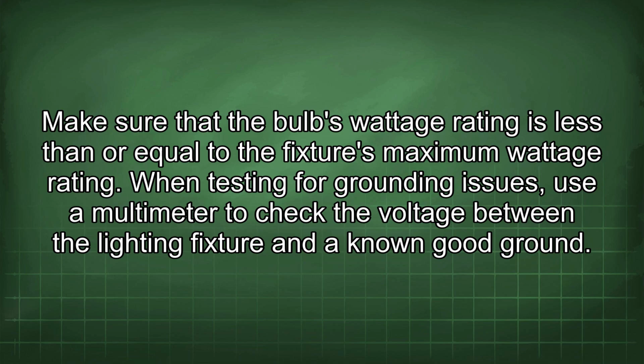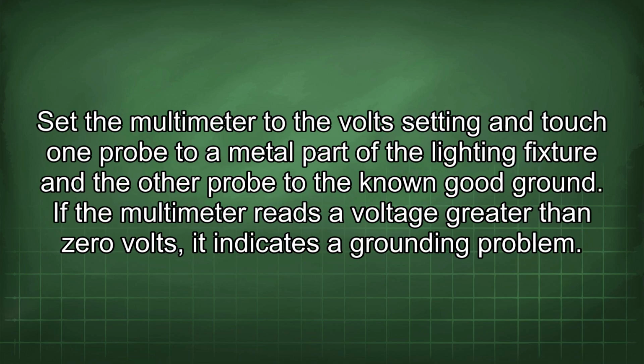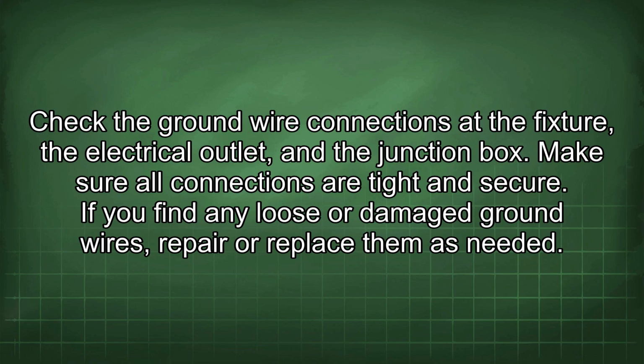When testing for grounding issues, use a multimeter to check the voltage between the lighting fixture and a known good ground. Set the multimeter to the volt setting and touch one probe to a metal part of the lighting fixture and the other probe to the known good ground. If the multimeter reads a voltage greater than 0 volts, it indicates a grounding problem. Check the ground wire connections at the fixture, the electrical outlet, and the junction box. Make sure all connections are tight and secure. If you find any loose or damaged ground wires, repair or replace them as needed.